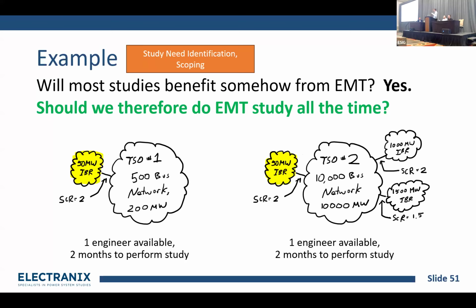Now we go over to the situation on the right. We have a new TSO number 2 with a 10,000 bus system and a 10,000 megawatt peak load, and now we've got 3 plants connecting — two very large ones, maybe offshore wind plants, with SCR 2 and SCR 1.5 — and then we have the same problem on the left: a 50 megawatt IBR connecting with an SCR of 2.